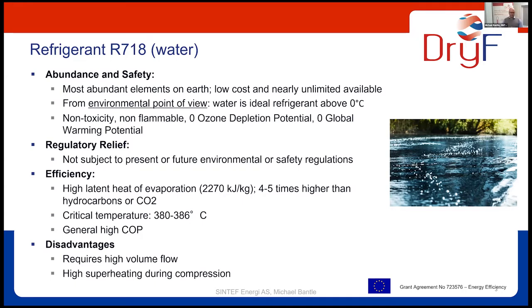Water basically requires a very high volume flow. At the pressure levels we are working at here, we have a very high volume to transport and to compress. That was the reason why we chose turbo compressors from Rotrex for this development. We also see that water is very easily superheated in the compression, so we have a very high degree of superheating, which is not so beneficial for practical reasons.